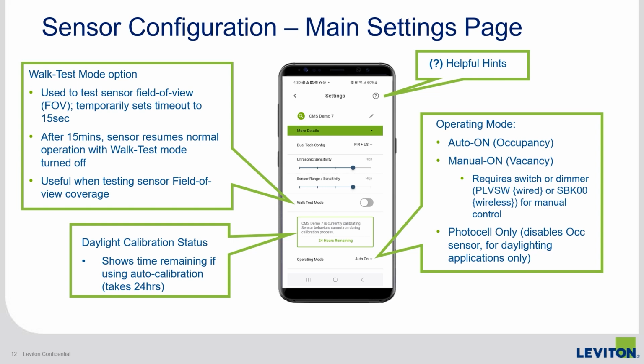Next on this page, you may see a daylighting calibration note. We'll have more on daylighting coming up, but this is where the status is located if currently in calibration mode. For the operating mode, there are 3 options. Auto on, also known as occupancy. In this mode, the lights or other loads will automatically turn on when occupancy is detected and will stay on until the space becomes vacant and the timeout expires.